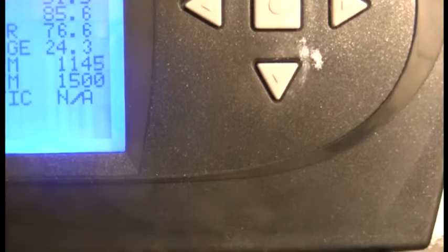This is a digital controller, and it's a diagnostic tool. It shows all of the basic information that you need to operate this system. It doesn't show in the video, but basically this will show you the entering water temperature when this unit is running now. Water's coming in at about 76.6, I'm sorry, about 77 degrees, which is the constant water temperature pretty much throughout Florida. And the water's leaving at 86.